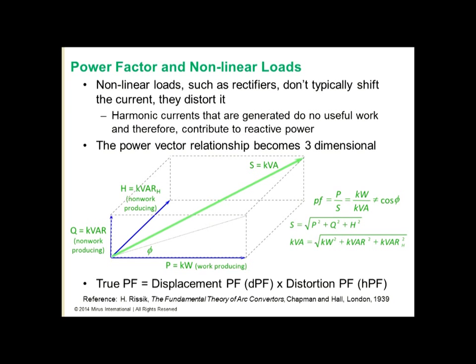In this graph we show that we still have the reactive power, inductive or capacitive. We now have a distortion harmonic component, and we have the real power in kilowatts. The distortion harmonic component is 90 degrees out of phase with the inductive or capacitive component and 90 degrees out of phase with the real work. The apparent power now in kVA is the vector sum of all three. So we've got the real power, the inductive or capacitive power, and the distortion reactive power to result in the full apparent power to be delivered.